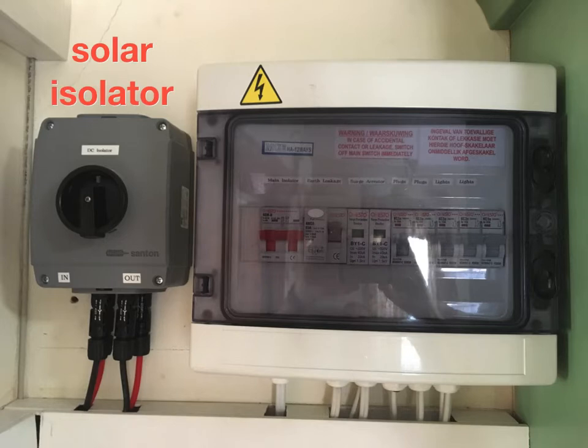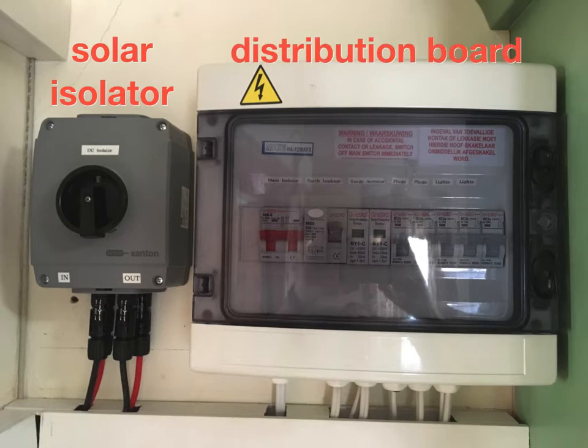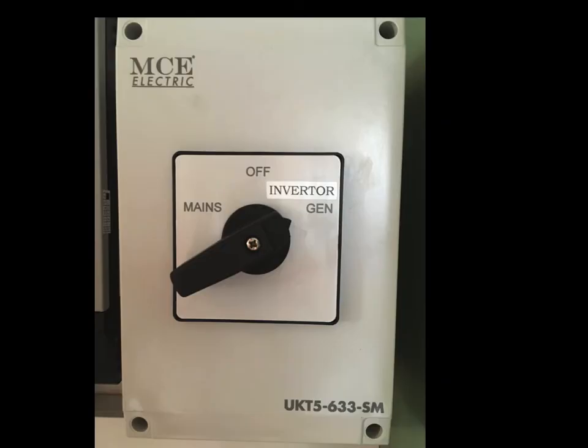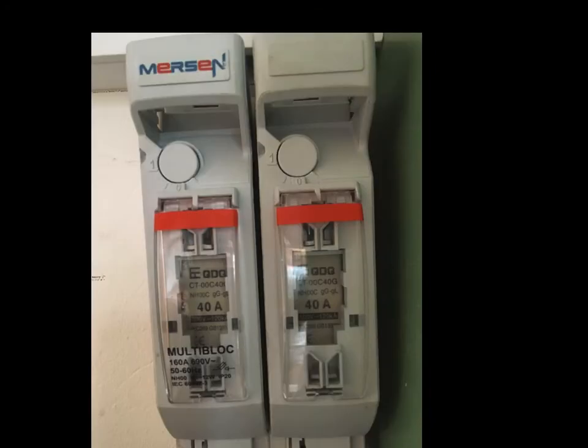Looking from the top down: first there's an isolator switch so we can turn the solar part of the system off if we need to. Then a distribution board — standard trip switches and earth leakage — specific to what is being backed up. Going down a level in my vertical rack is the inverter, which does all the smart voltage conversions and has a little control panel. There's also something that allows me to switch power source — the 'generator' label is a bit misleading because there isn't one; it's just too long to fit in the space. This allows me to switch the whole thing off, run off the inverter which does smart switching between power sources, or switch it straight to mains. Normally I just leave it in that position. Next down in the picture there are two monster fuses that go between the battery and the rest of the system, so if there's a huge power surge I don't fry the batteries, or if the batteries behave badly they don't fry the rest of the system.